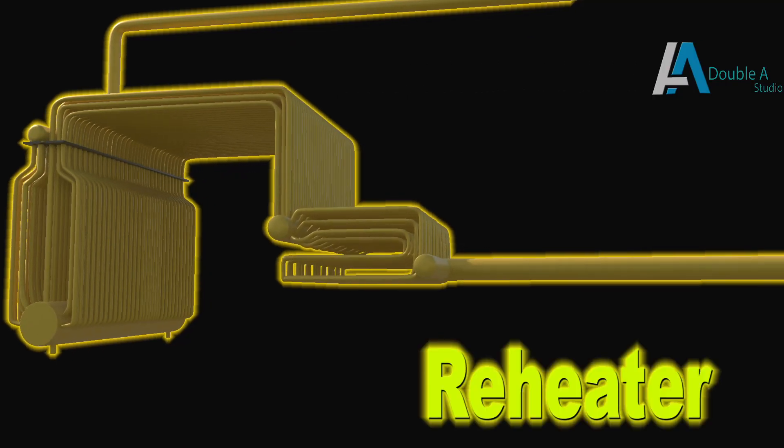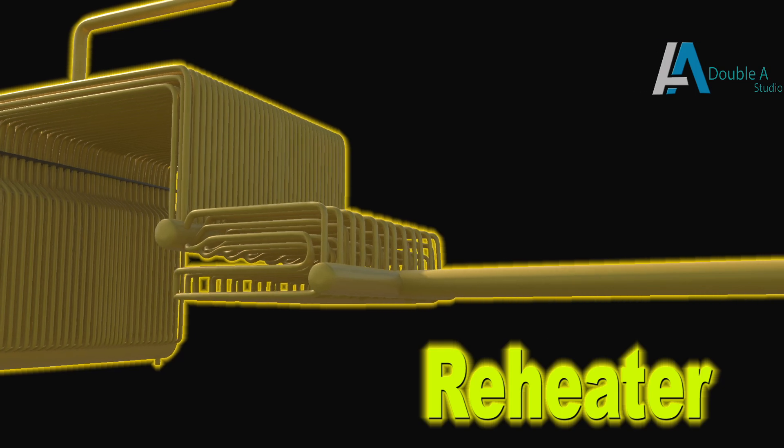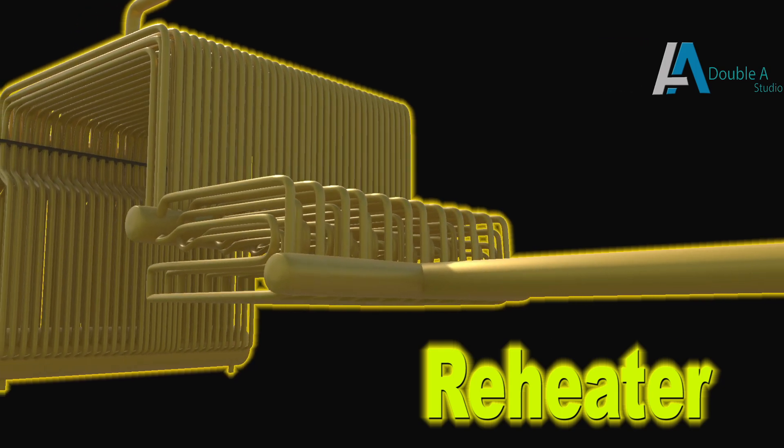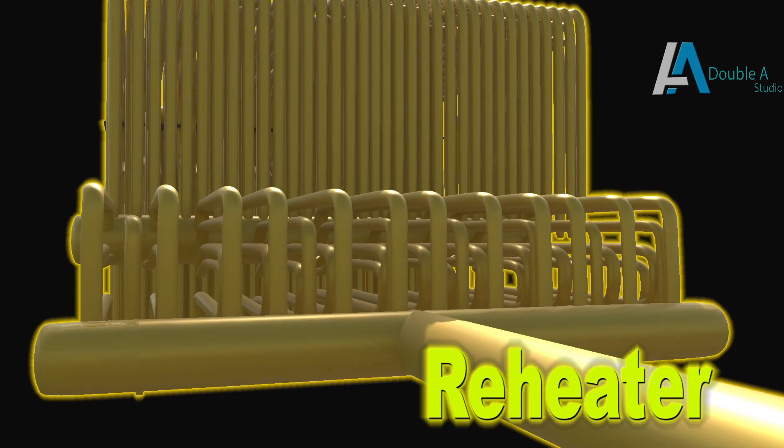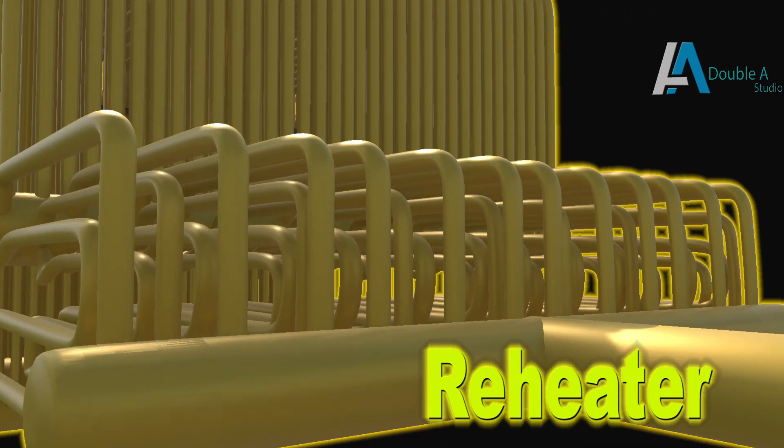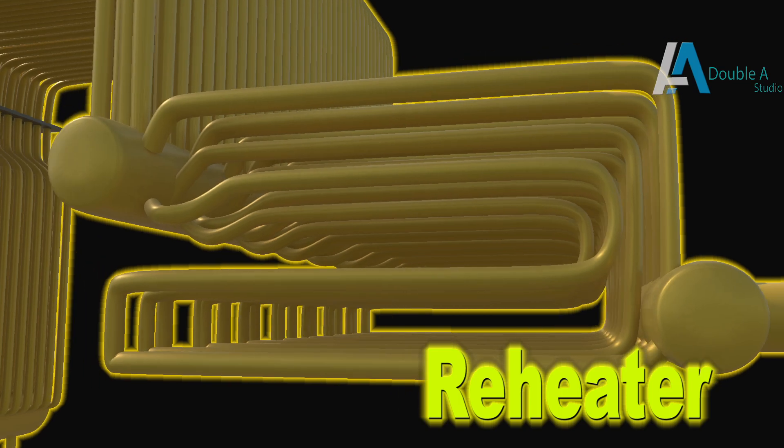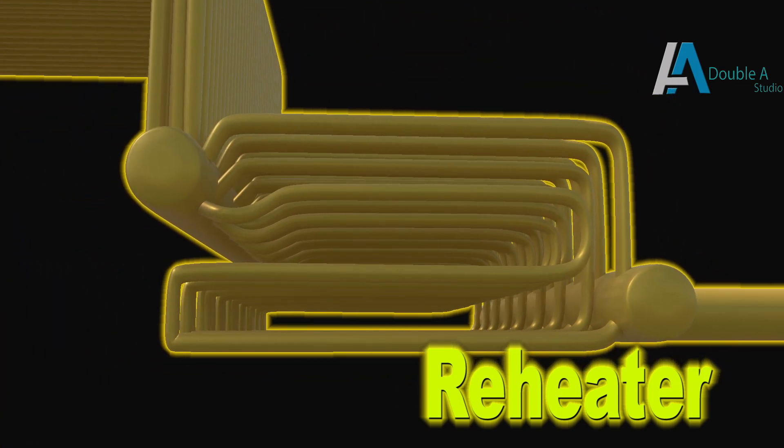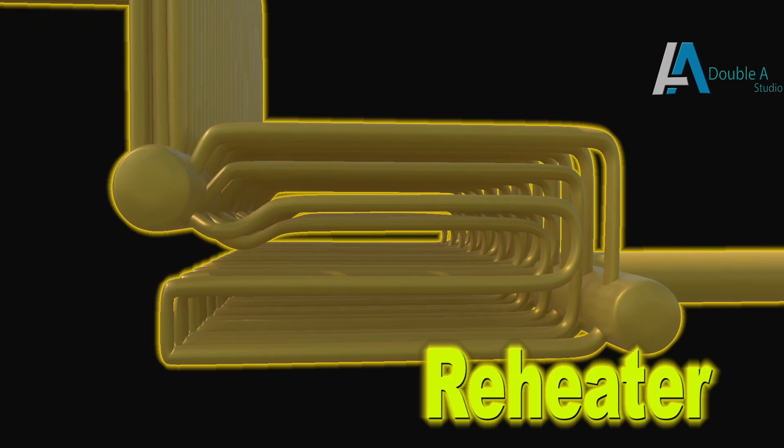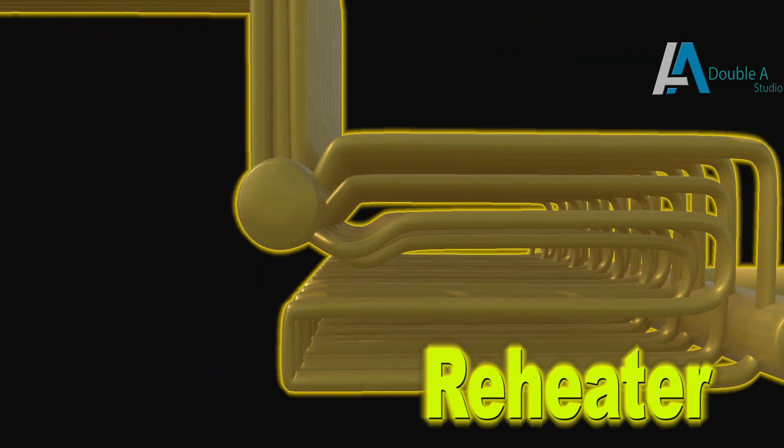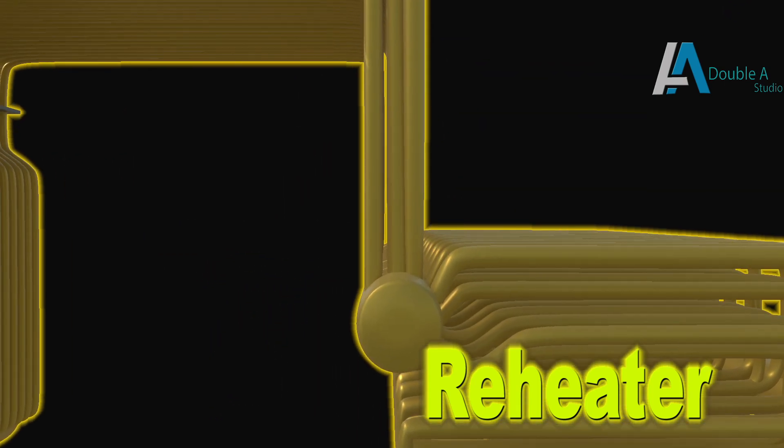First comes the reheater which is again a tubular heat exchanger. Its function is to reheat steam coming out of the HP turbine. Reheater increases temperature of the steam and reheated steam is sent to the intermediate and then lower pressure turbine for further expansion and work.